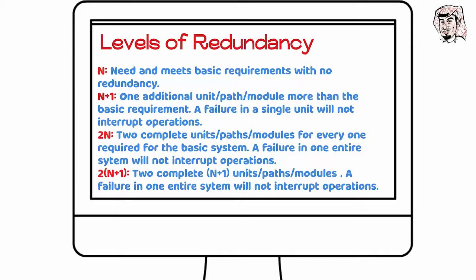Levels of redundancy. N represents need, and meets basic requirements with no redundancy. N+1 comes with one additional unit, path, or module more than the basic requirement. A failure in a single unit will not interrupt operations. 2N has two complete units, paths, or modules for every one required for the basic system. A failure in one entire system will not interrupt operations.